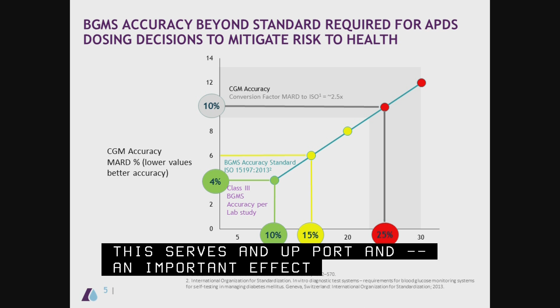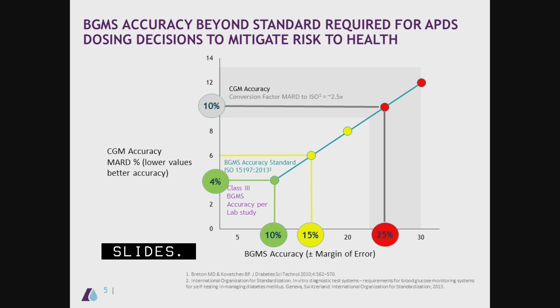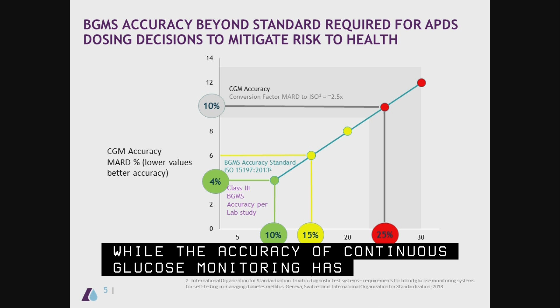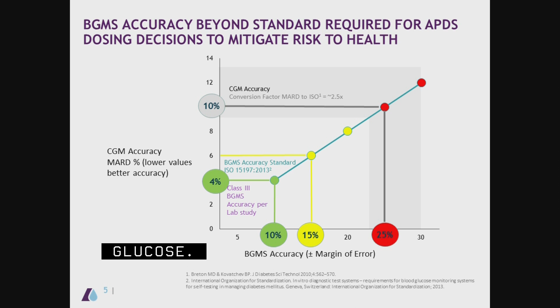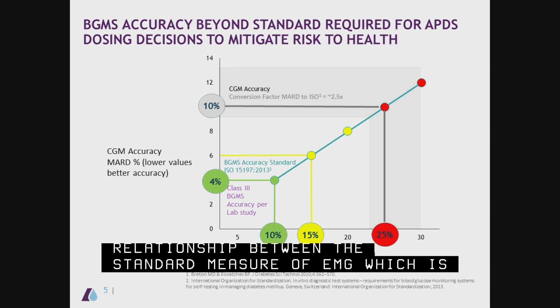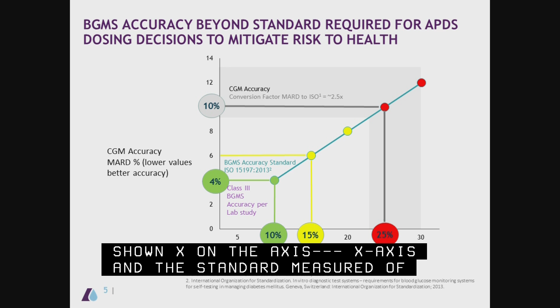While the accuracy of CGM systems, continuous glucose monitoring systems, has improved dramatically, it is still a long way to go before it achieves the accuracy levels afforded by directly measuring blood glucose. This slide here shows the approximate relationship between the standard measure for BGM, which is shown on the x-axis, which is plus or minus a margin of error to a lab reference, and the standard measure of a CGM, which is MARD, or mean absolute relative difference, shown on the y-axis.